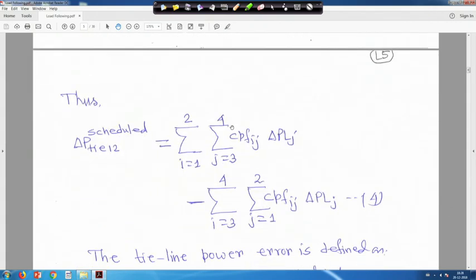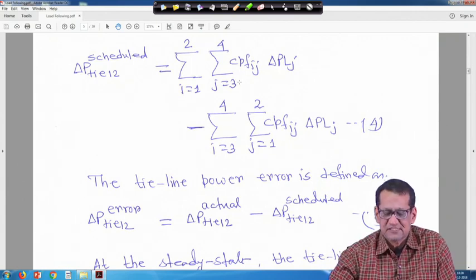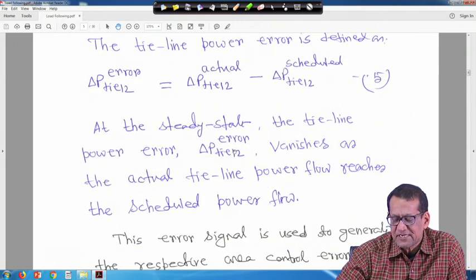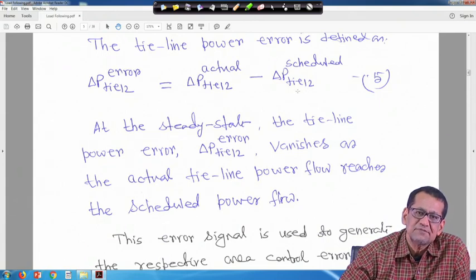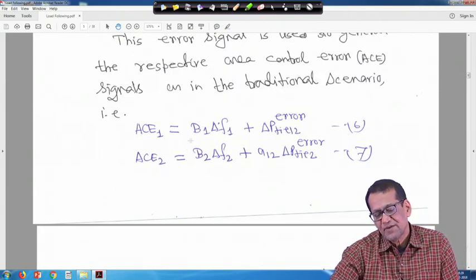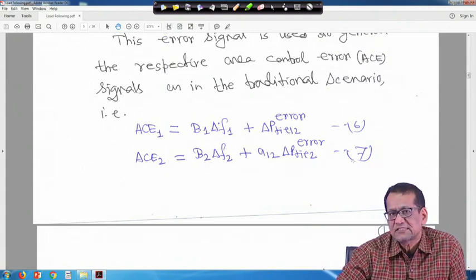Delta P_tie_12_scheduled is given by: sigma (i=1 to 2, j=3 to 4) CPF_ij * delta_PLj minus sigma (i=3 to 4, j=1 to 2) CPF_ij * delta_PLj — this is equation 4. The tie-line power error is defined as delta P_tie_12_actual minus delta P_tie_12_scheduled. At steady state this error vanishes, so delta P_tie_12_actual equals delta P_tie_12_scheduled. The error signal generates the area control error: ACE1 = B1 * delta_F1 + delta P_tie_12_error, and ACE2 = B2 * delta_F2 + A12 * delta P_tie_12_error (equation 7).